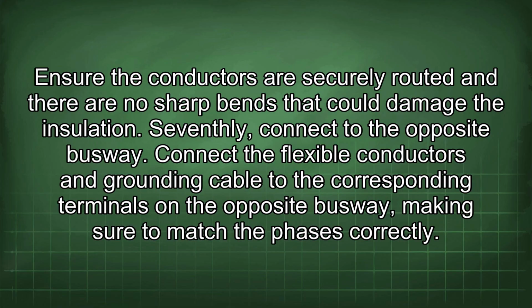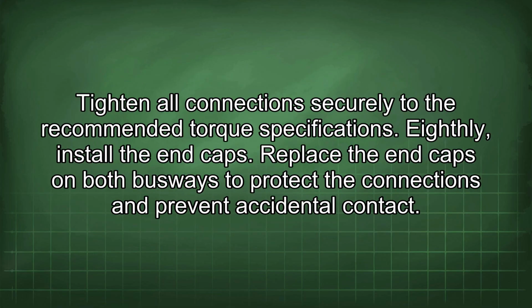Seventhly, connect to the opposite busway. Connect the flexible conductors and grounding cable to the corresponding terminals on the opposite busway, making sure to match the phases correctly. Tighten all connections securely to the recommended torque specifications. Eighthly, install the end caps. Replace the end caps on both busways to protect the connections and prevent accidental contact.